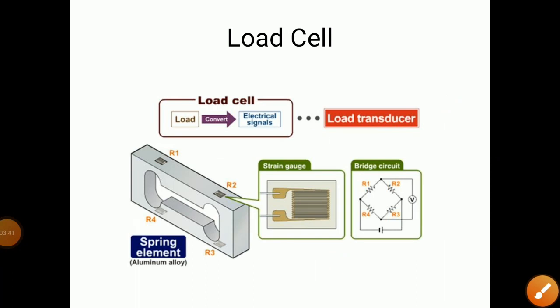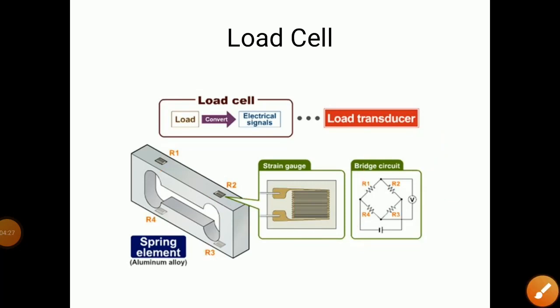This is the diagram of load cell. Load is converted into electrical signals — that is a load transducer. Load cell consists of strain gauges. In this diagram, four strain gauges are connected: R1, R2, R3, and R4. All four strain gauges are connected as resistances in the Wheatstone type bridge circuit, and the voltage produced is measured. So in the load cell, strain gauges are used, and force applied is converted into electrical signals.